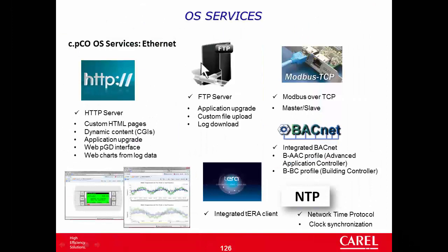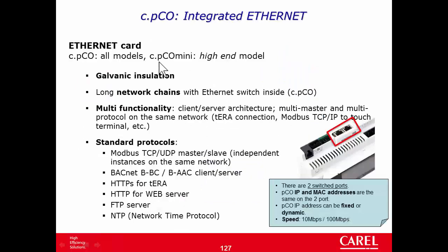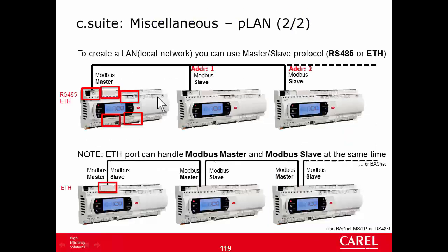Operating system services — Ethernet. The Ethernet card is available in all c.pCO models, and in c.pCOmini only in the high-end model. It provides galvanic insulation. There is one Ethernet card with one IP and one MAC address. c.pCO has two switched ports with a built-in two-port switch, which allows long network chains — you can enter from one port and exit from the other without an external switch.